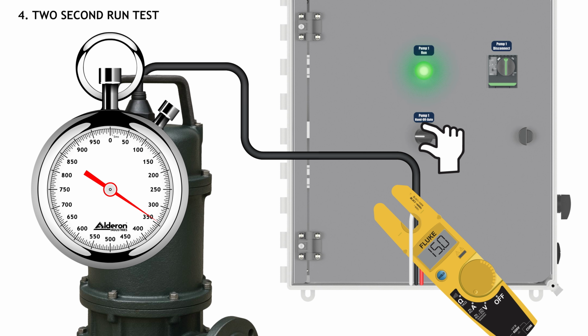After 2 seconds, place the HOA switch to off to stop the pump. Third, determine the result of the amp reading. If the amps are less than 15, then the system can be further evaluated by filling the tank with water and running the system longer. If the pump is pumping water and the amps remain under 15 while running longer, then congratulations. You have successfully wired the pump to the panel correctly.